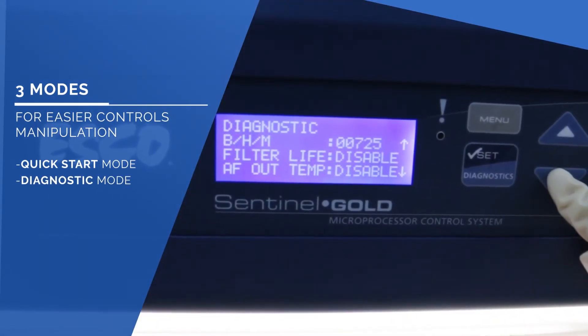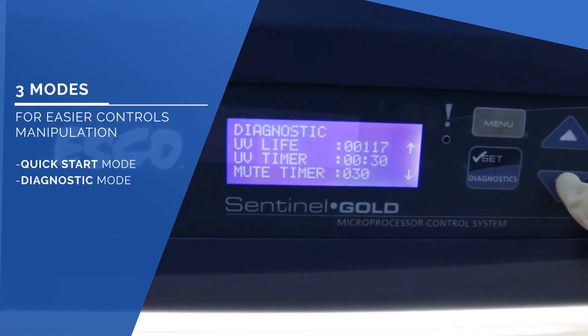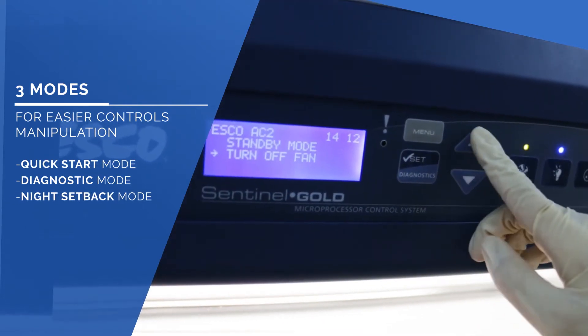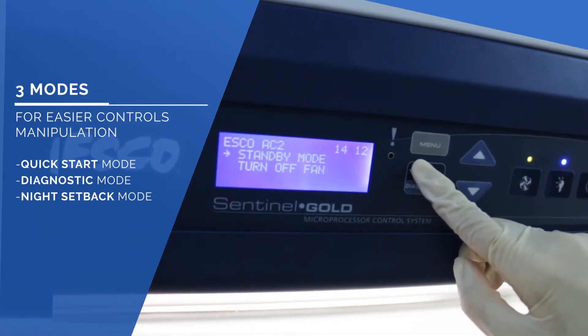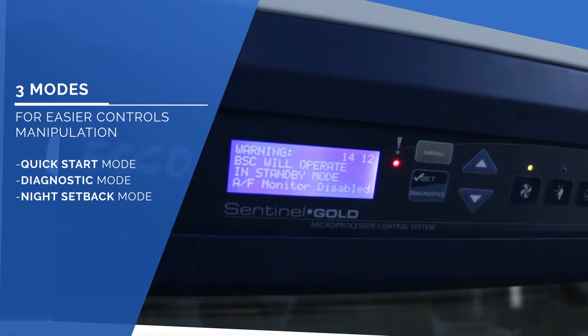Diagnostic Mode for easy checking of the cabinet's operating parameters and assist servicing. And Night Setback Mode that can provide maintained containment even at energy-saving mode with the fan running at half speed.